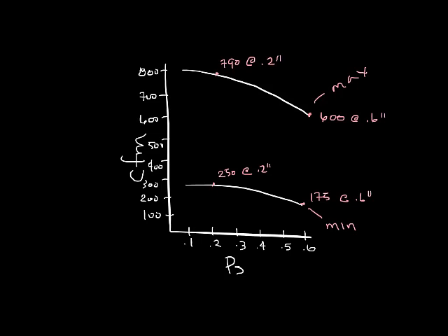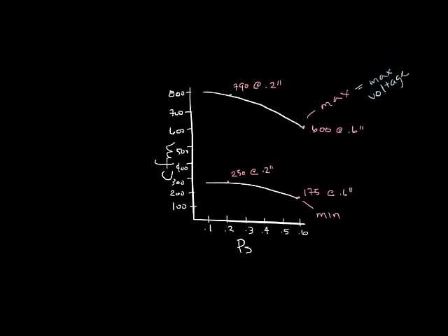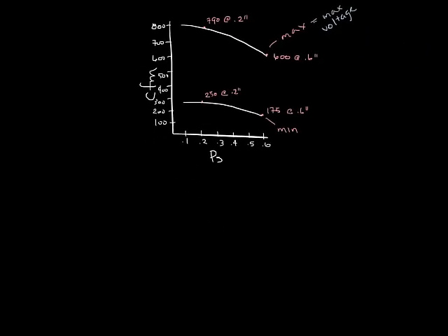So where do the maximum and minimum fan box curves come from? The maximum fan curve is basically the fan operation at full voltage. Before we talk about the minimum fan curve line, let's talk about the most common way to reduce the airflow of a fan box. Let's scoot this out of the way.